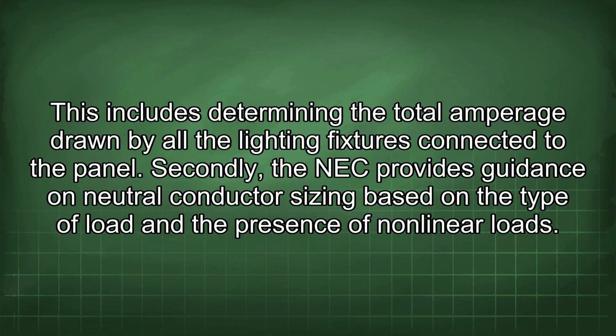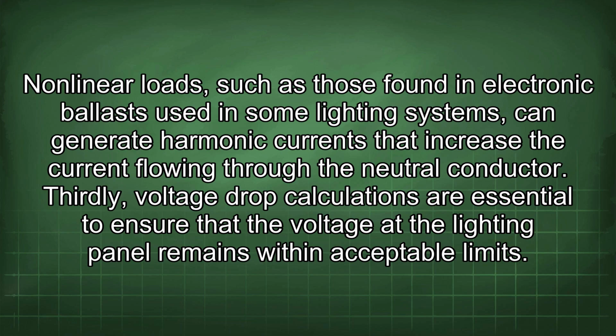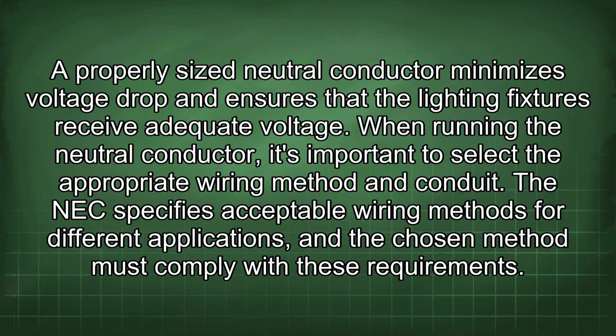Secondly, the NEC provides guidance on neutral conductor sizing based on the type of load and the presence of nonlinear loads. Nonlinear loads, such as those found in electronic ballasts used in some lighting systems, can generate harmonic currents that increase the current flowing through the neutral conductor. Thirdly, voltage drop calculations are essential to ensure that the voltage at the lighting panel remains within acceptable limits. A properly sized neutral conductor minimizes voltage drop and ensures that the lighting fixtures receive adequate voltage.